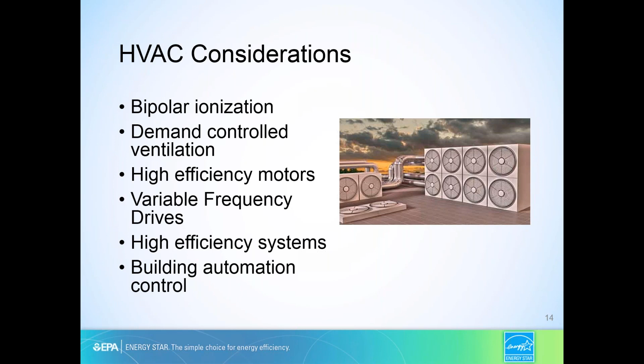Make sure you have high efficiency motors. Make sure your demand controlled ventilation, if you have that, is working properly. And what I mean by demand controlled ventilation is if we have hot, humid outside air that needs to be brought into a building to satisfy ASHRAE 62.1, to satisfy your building code requirements, make sure that you're only bringing in enough of that air that you need to, right? So if you have a conference room or if you have a large office space, you're going to need to bring in that outside air. You need to treat it. You need to wring out the moisture through your HVAC system, but that costs a lot of money. It's a lot of energy to be able to do that. But if you don't have a lot of people in the space, or it's a conference room that's not being used, you should be able to back down that outside air system so that you're reducing the load on your HVAC system.